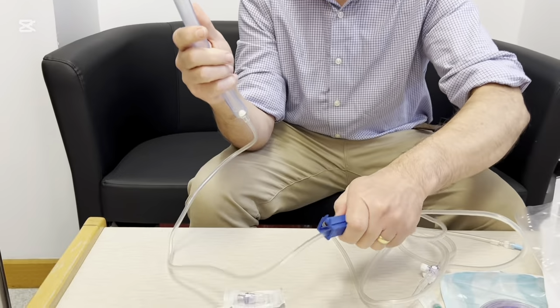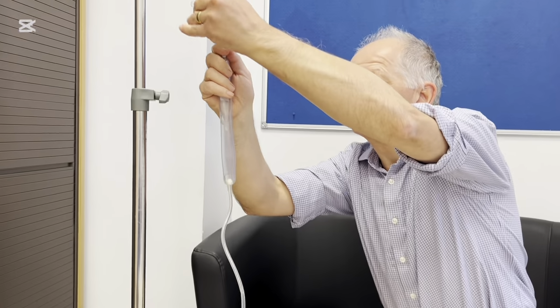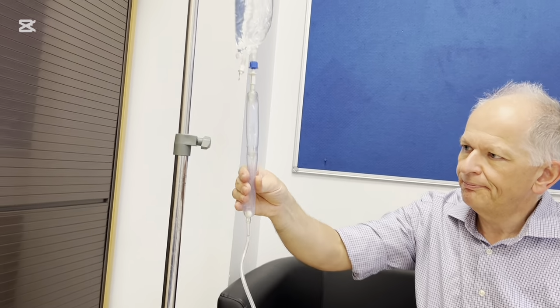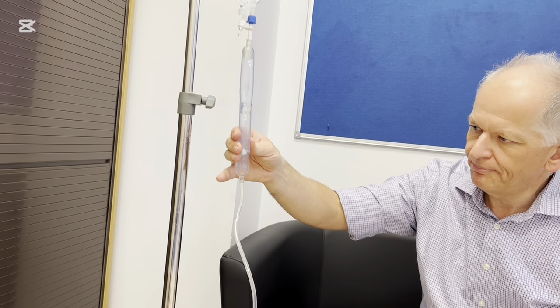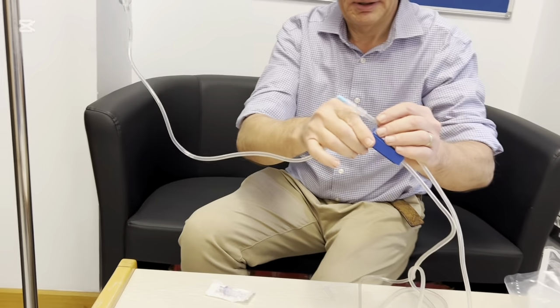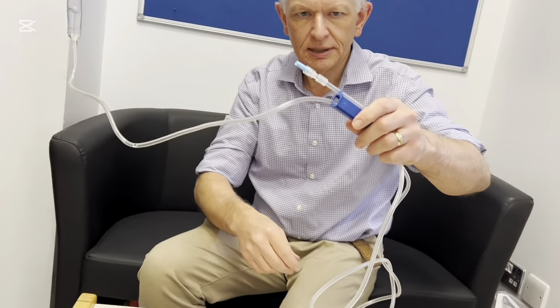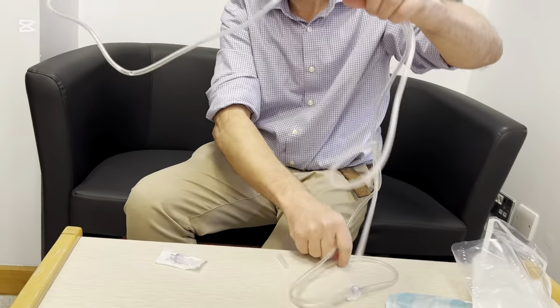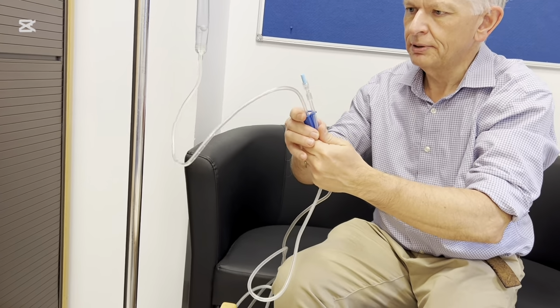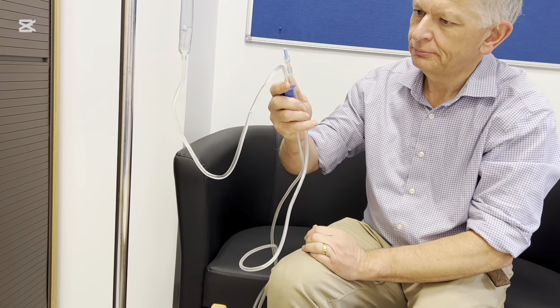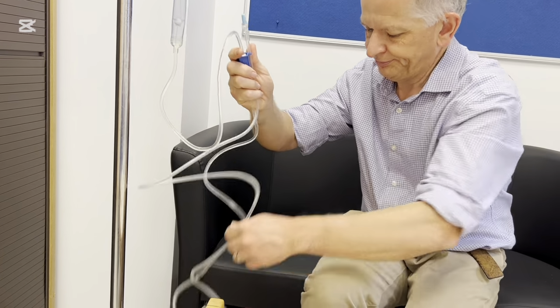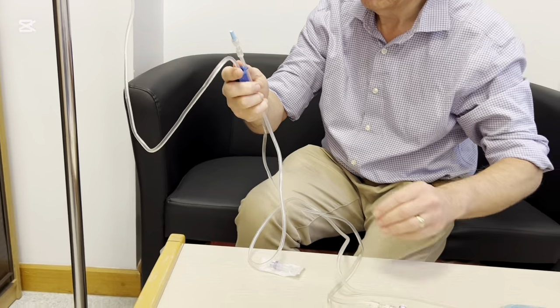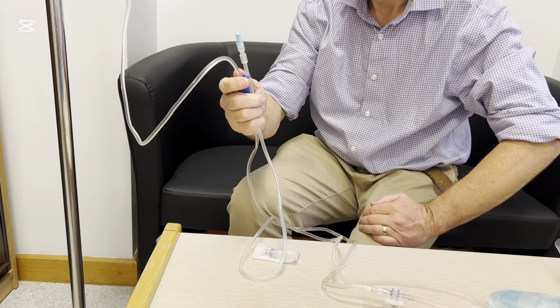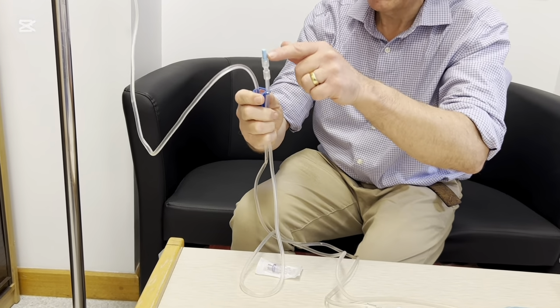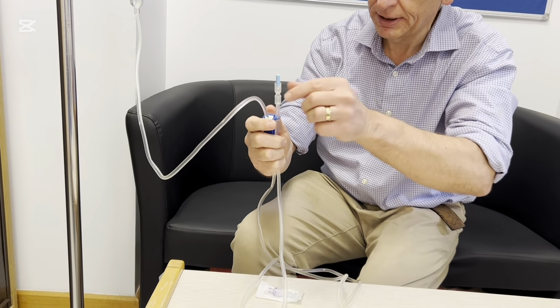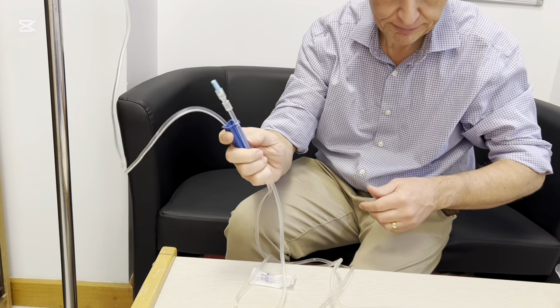Again, close the roller clamp, spike the bag, prime the chamber with fluid. Again, you can just put the extension set into the clip on the roller clamp and just open the roller clamp and allow the set to prime. Click end cap, so once the fluid has reached the end stop, it'll automatically stop.